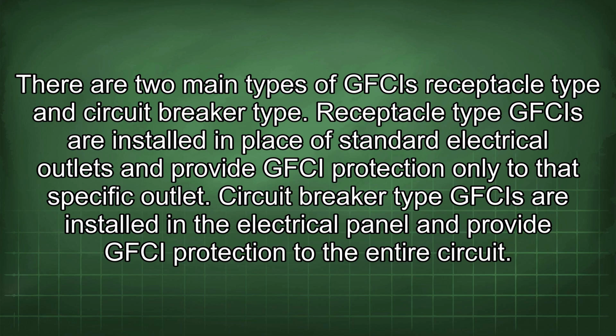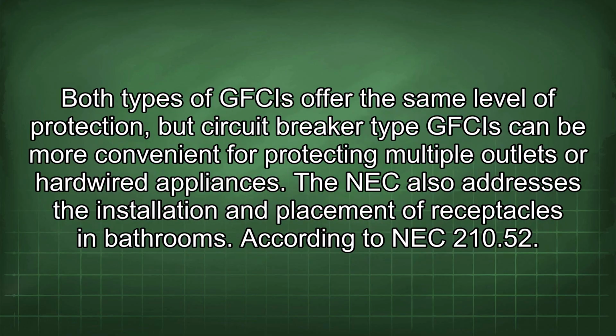There are two main types of GFCIs: receptacle type and circuit breaker type. Receptacle type GFCIs are installed in place of standard electrical outlets and provide GFCI protection only to that specific outlet. Circuit breaker type GFCIs are installed in the electrical panel and provide GFCI protection to the entire circuit. Both types of GFCIs offer the same level of protection, but circuit breaker type GFCIs can be more convenient for protecting multiple outlets or hardwired appliances.